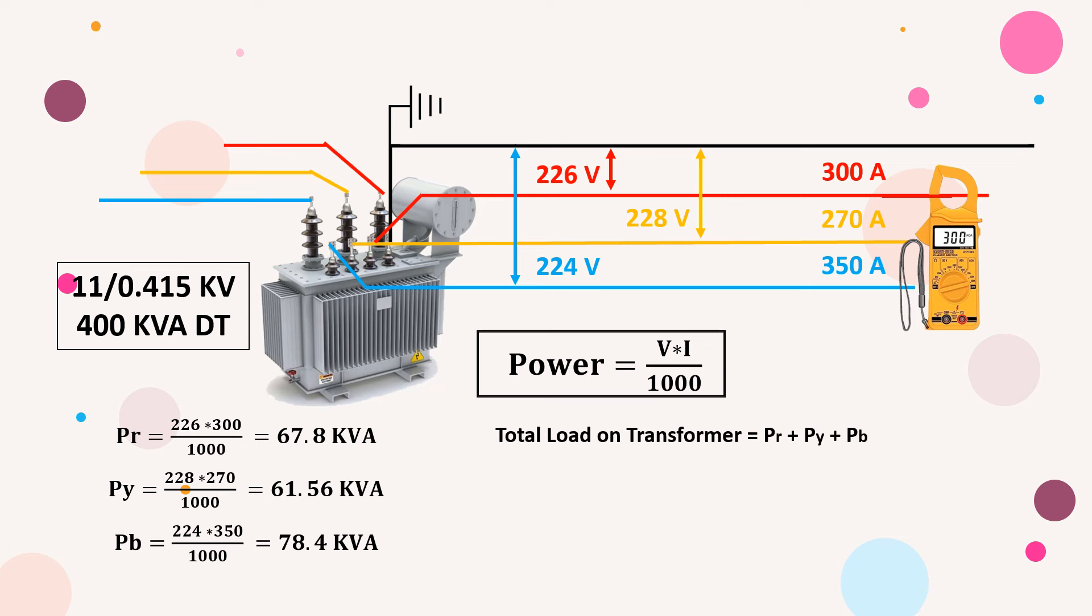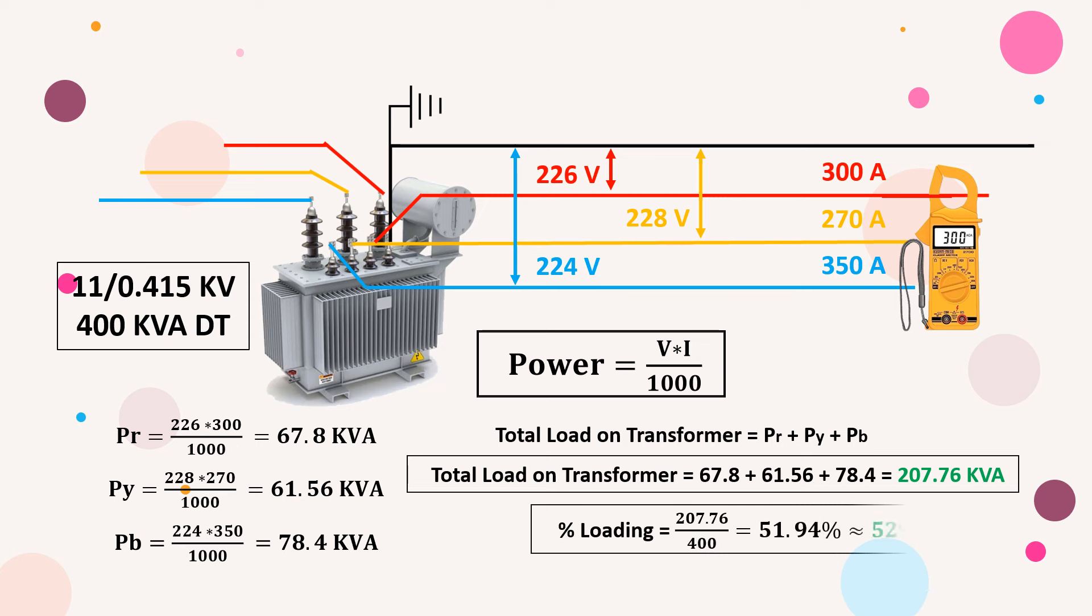Add these kVAs of all three phases and say that the total load connected on this transformer is 207.76 kVA. Now if you further divide this value by the transformer's rating, you can simply say that this transformer is 52% loaded.